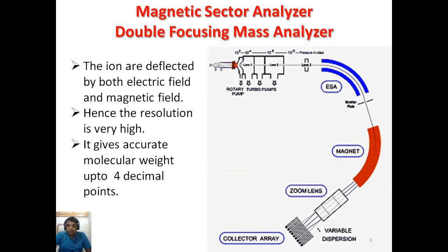The circular paths in the electrostatic analyzer and magnetic analyzer provide a very accurate separation of the molecules from each other, as well as very accurate mass up to 4 decimal places. The magnetic analyzer also takes care that molecules do not agglomerate. Hence you get a very precise mass up to 4 decimals for each fragmented molecule.